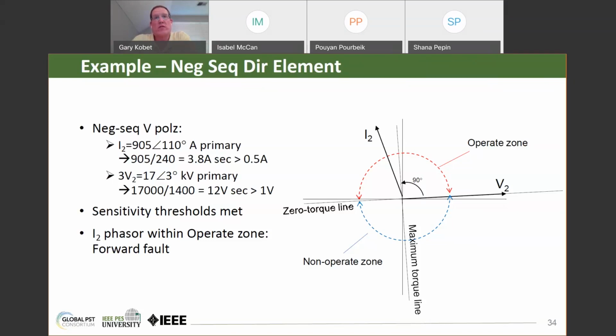In cases where the negative sequence quantities are below the thresholds, the relay cannot make a directional decision. And so with large penetrations of inverter-based resources, there is a possibility that there will not be enough negative sequence for a directional element to make the proper decision. And that has already happened in a couple of places in North America. And so this is an issue that the industry is going to have to deal with somehow.